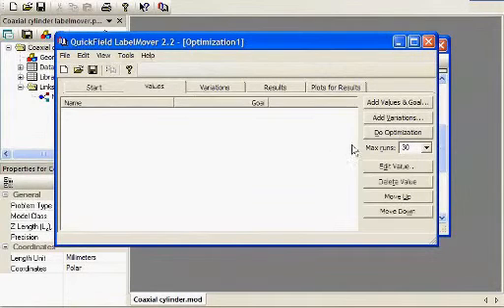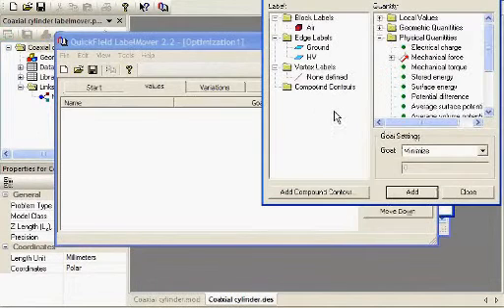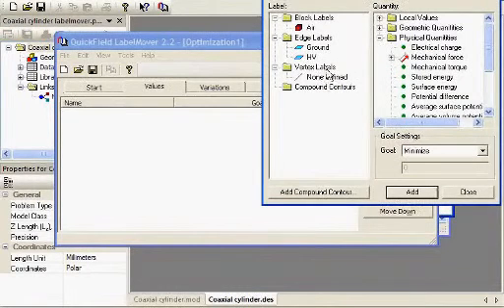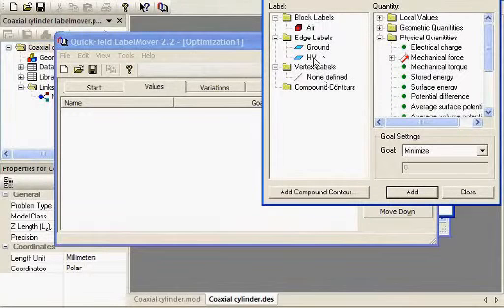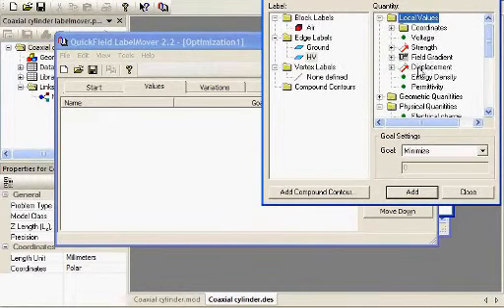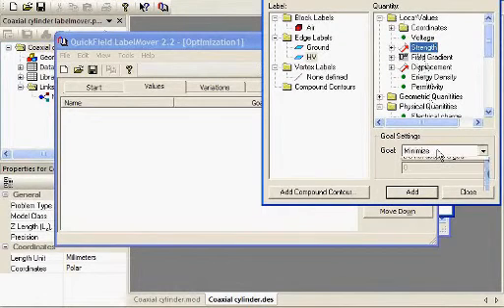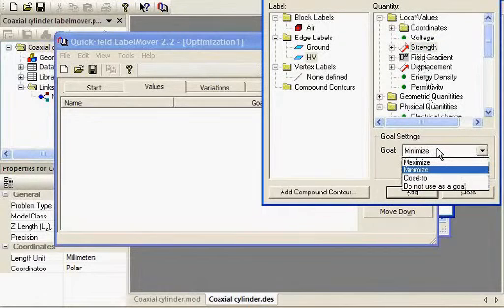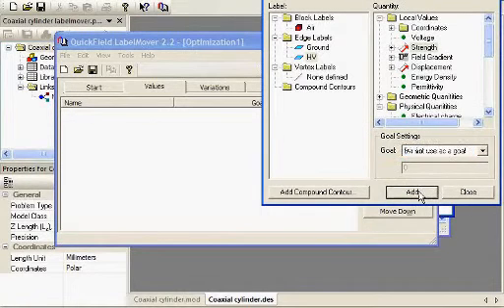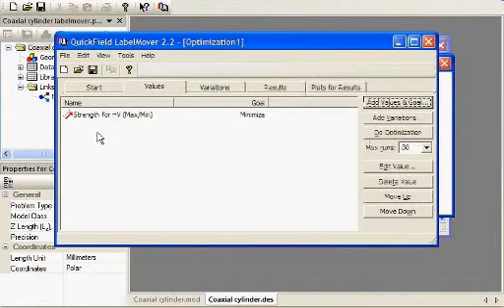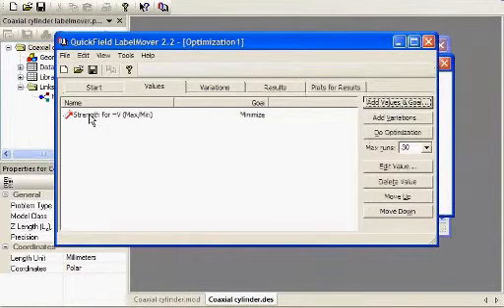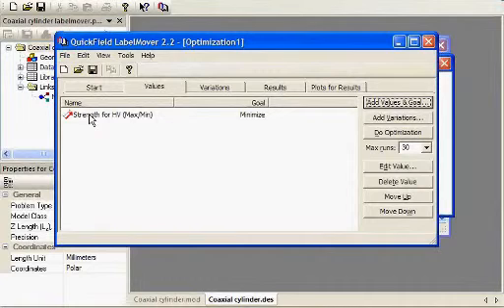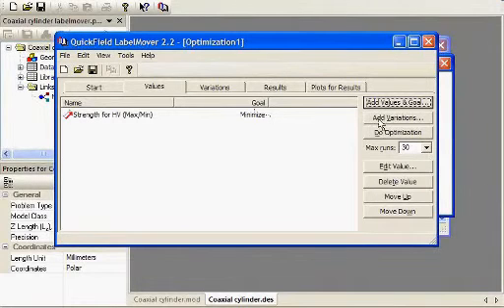We've defined the base problem. The next thing is to pick the values. We can go over here and add values in the goal. You can see it gives you a number of different things to select from. I'm going to pick the high voltage edge and pick the local value of the field strength. You can see the goal settings. I'm going to go ahead and pick Minimize, and then add that and close it. So what this is going to do in the optimization process is try and minimize the field strength at that outside diameter of the inner conductor on the cable.